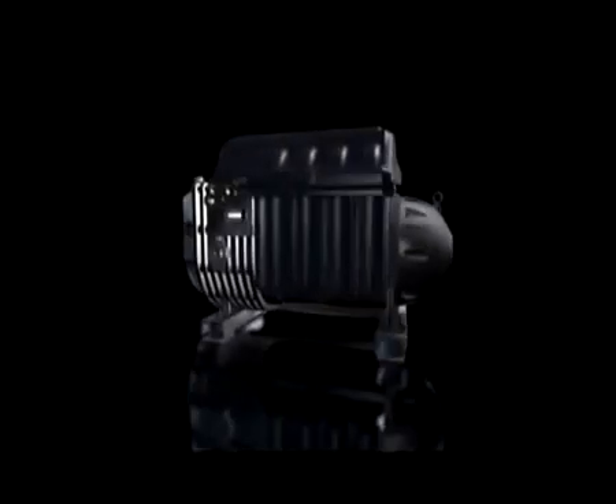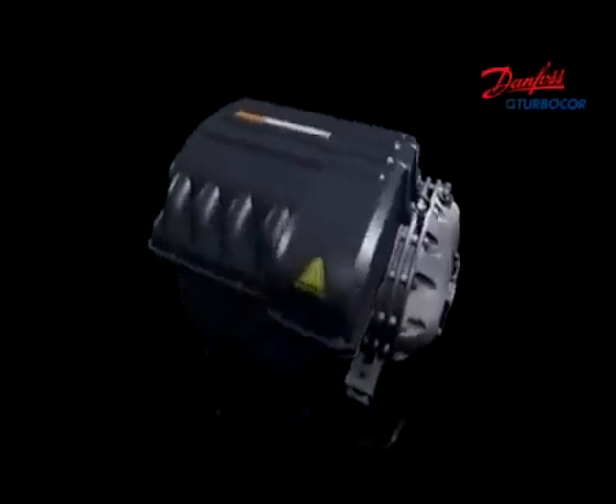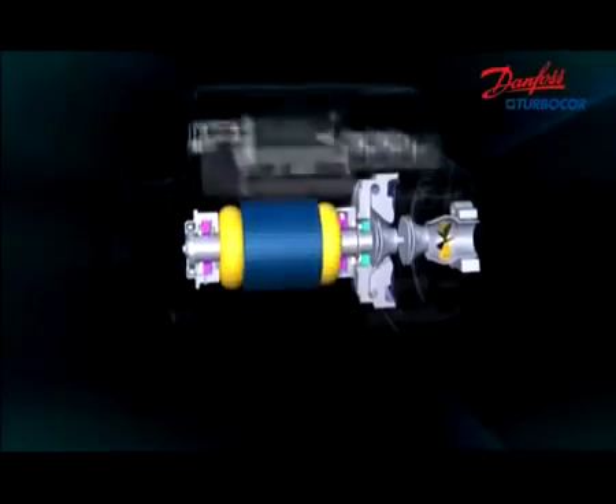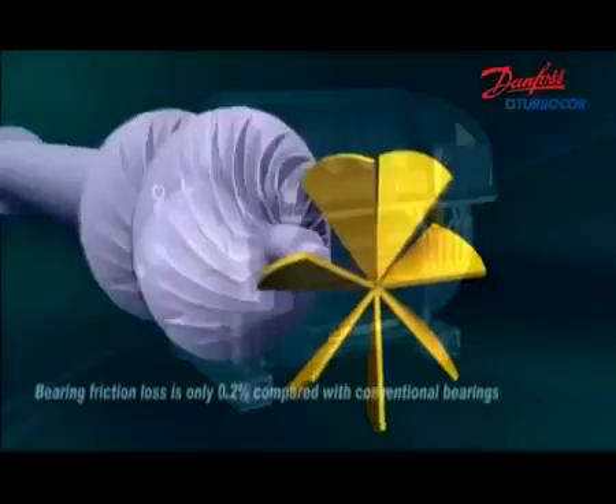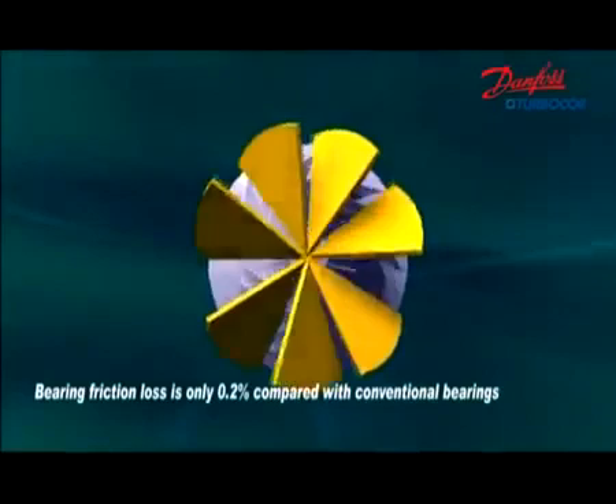Danfoss Turbocor is the first magnetic levitation bearing and variable speed driven centrifugal compressor in the world. It is composed of two-stage centrifugal compression, magnetic bearings, high-speed permanent magnet motor, compressor control, motor and bearing control, and condition monitoring. The rotor and impeller are the only moving parts, which ensures high reliability.